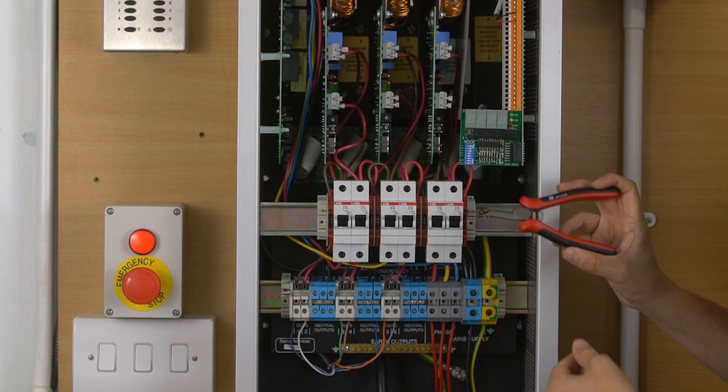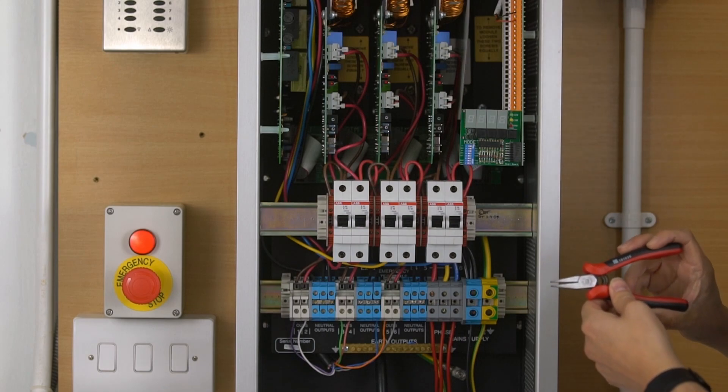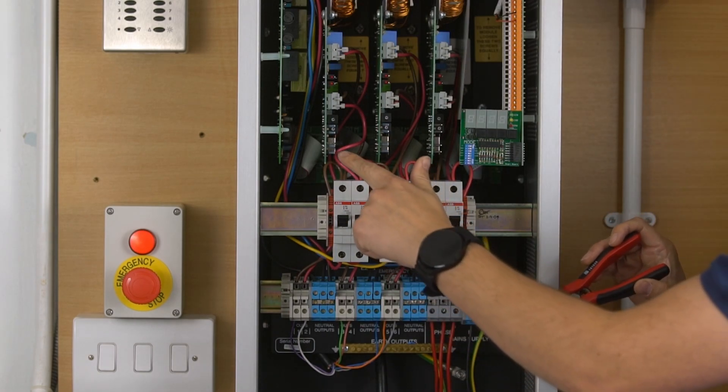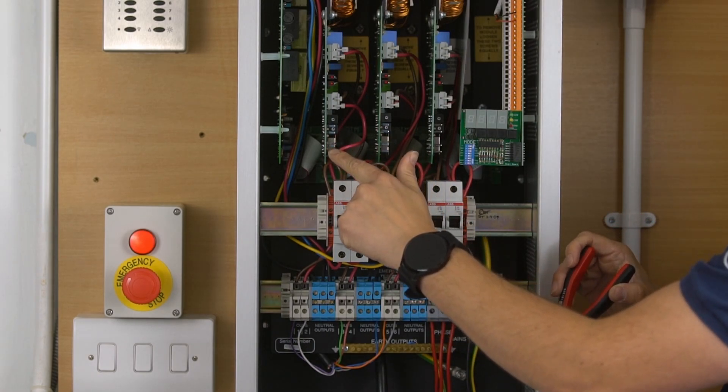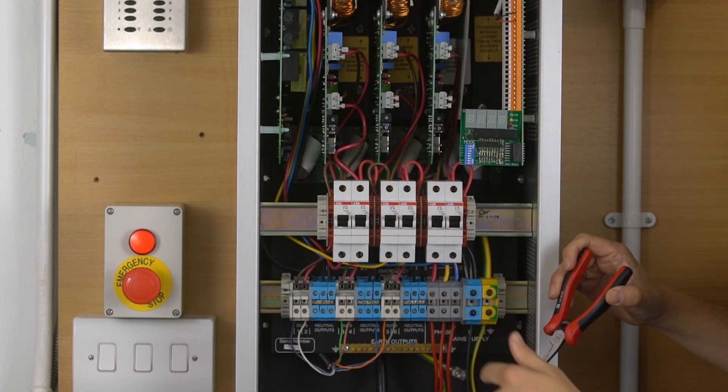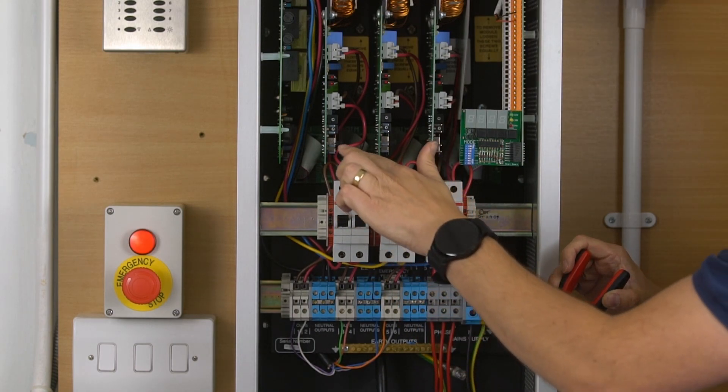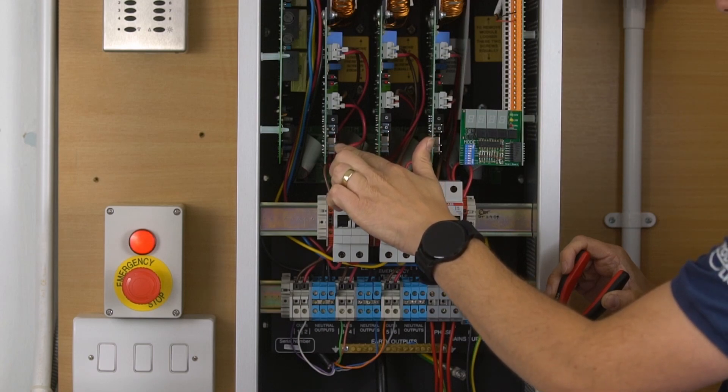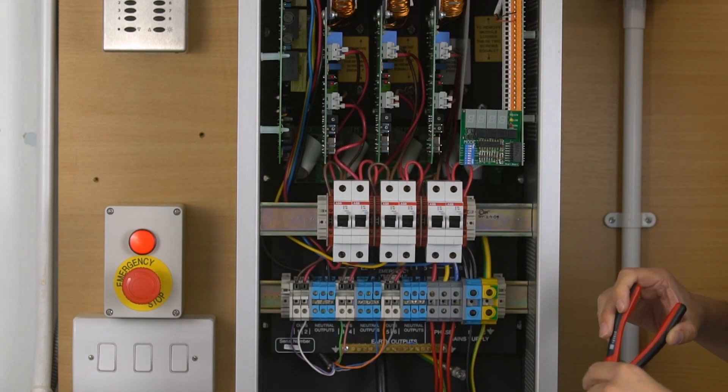At this point you should set if your circuits are dimmable or non-dimmable. This is done with the jumper links at the bottom of the dimming cards. When the jumper link is in the back position, this is how they're set out of factory, the circuit will dim.